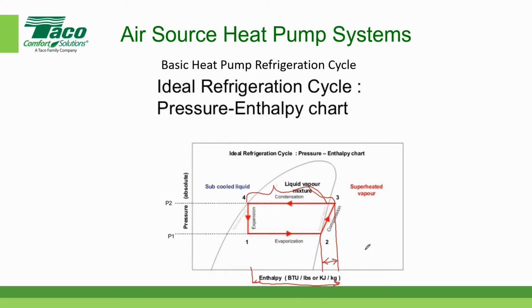So the work of the compressor is relatively small compared to the amount of heat that we can either reject or absorb either through the condenser or the evaporator. And that's important when we get into the next part, when we start talking about the coefficient of performance. Any questions about the refrigerant cycle?